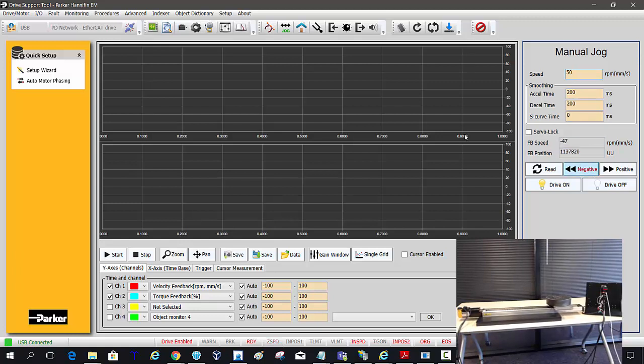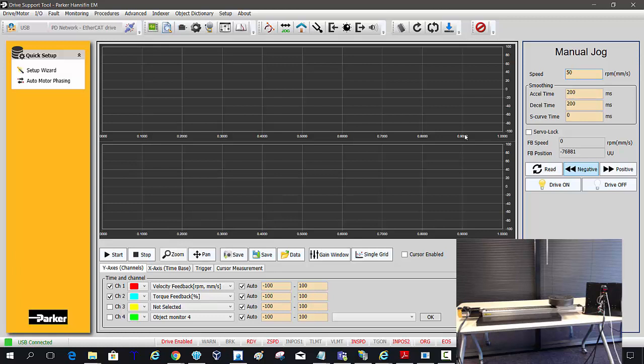The P-series motors have a high resolution absolute encoder. The 60 and the 80 millimeter frame size have a 19 bit resolution encoder which is 524,288 counts per revolution. The 40 millimeter which is a PMFAL is 18 bit which is half of that, so it's 262,144 counts per revolution.